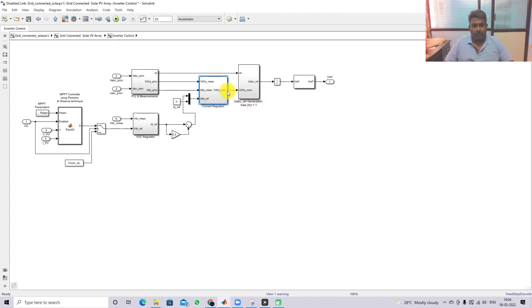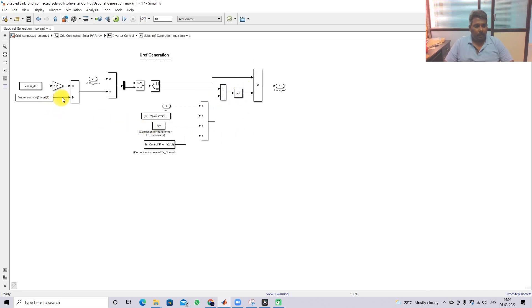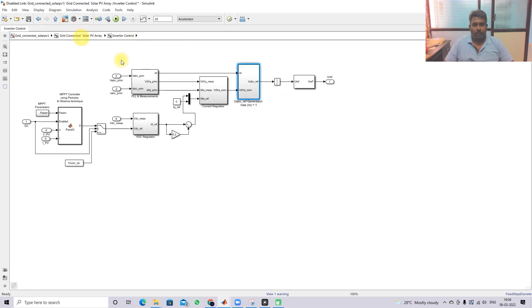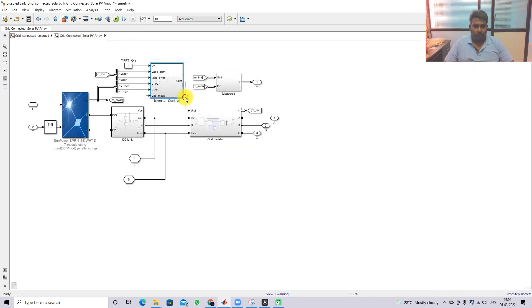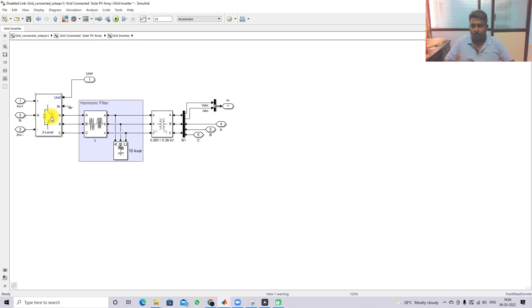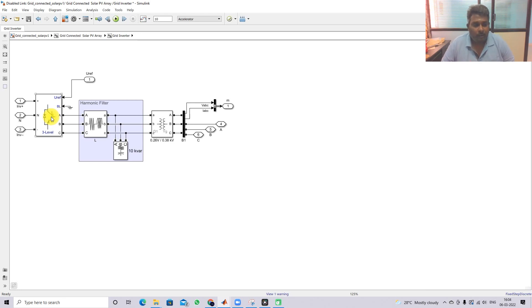After the current controller generates the controlled voltages vd and vq, they are converted back into abc reference form. The abc references are then processed by an overmodulation PWM generator, which generates the reference voltage signals for the neutral point clamped inverter. The NPC inverter then controls the power flow from the solar PV and battery to the grid side.